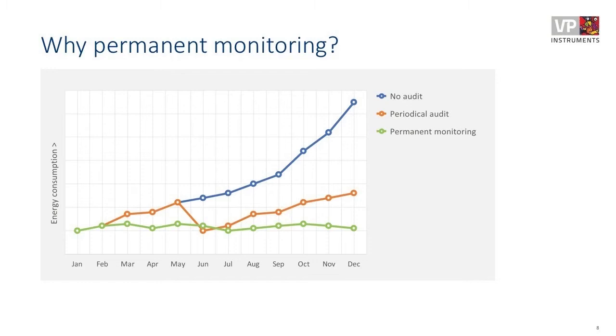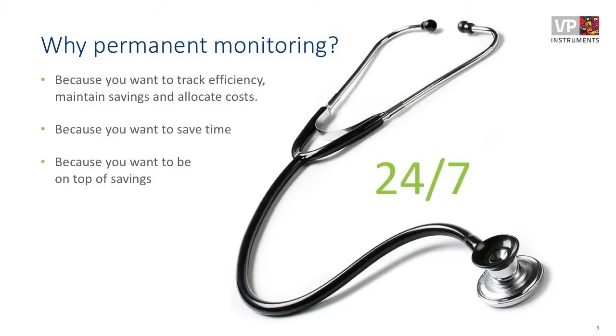So that's why we are strong believers in permanent monitoring. It will keep your efficiency basically at the best possible level. It will keep your leakage level at the lowest possible level. And there are other reasons as well. Permanent monitoring will save you time because the system will do a lot of work for you, so you don't have to run around all the time. No, you will get an alarm or an alert message when something goes out of whack. And you also know where to look.